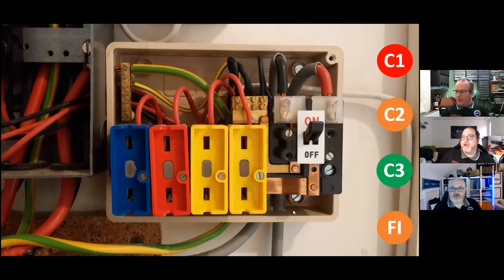Well, this is one of mine. So actually got to them. This did have a cover on it originally, and it did have fuses in it as well. So that's obviously been taken out. The thing to look at here is the fact that these are rewirable fuses, 3036 sticks, and also look at what conductors are attached to each of the fuses in there and relevant to the values of those fuses. It looks lovely and clean though, doesn't it?